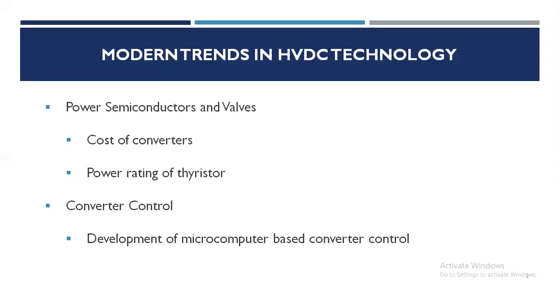The use of a mini simulator will make it feasible to check vital control and protection functions. The microcomputer based control also has the flexibility to try adaptive control algorithms or even the use of expert systems for fault diagnosis and protections. The control and protection requires the measurement of direct current. Traditionally, the direct current is measured using transducers of zero flux type based on magnetics, which are bulky and prone to problems during transients.